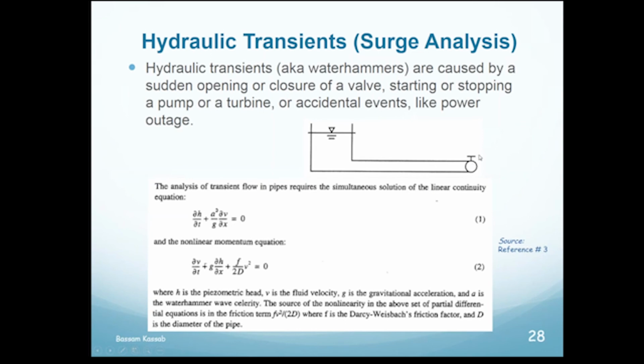So shutting off a valve, or even opening it abruptly, could cause that. Stopping or starting a pump or a turbine can do that. Any event like a power outage can cause that. So transients can happen in the system, and that's why you want to understand the severity - to see if you have to design the pipe thicker or with a different material to withstand such transients. And also to tell your operators: please do not shut the valve in less than 10 or 20 seconds. Take the time to shut it off so you don't generate a large transient.